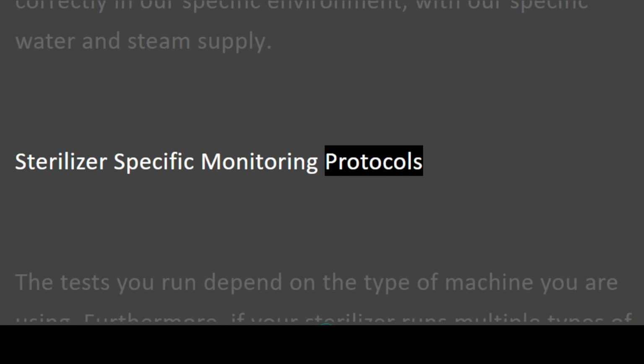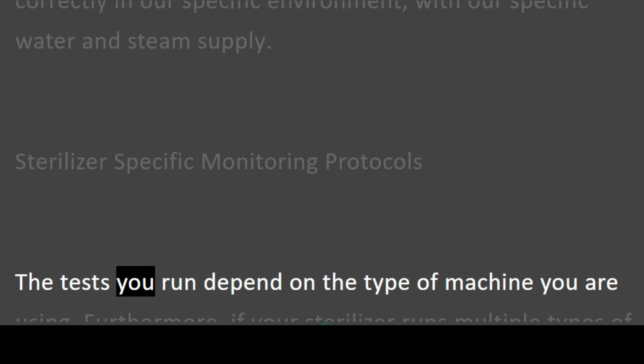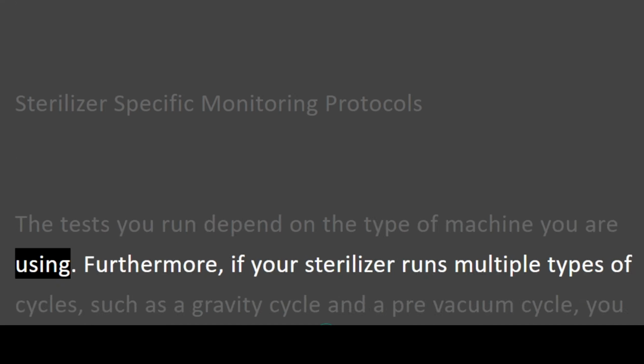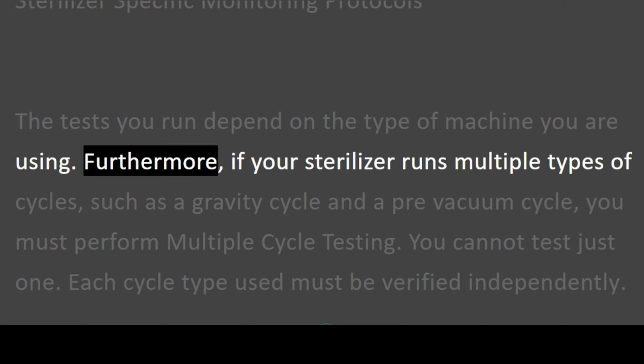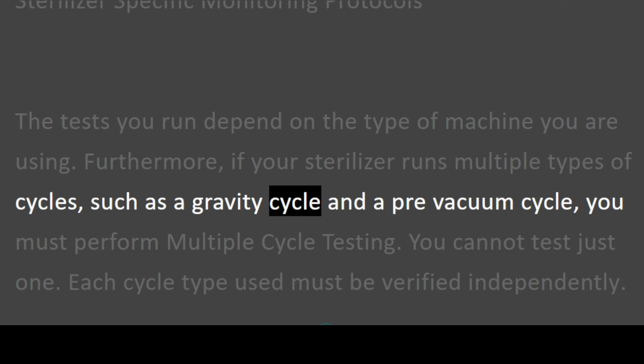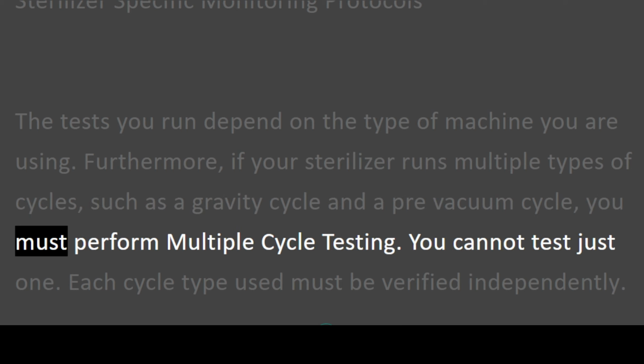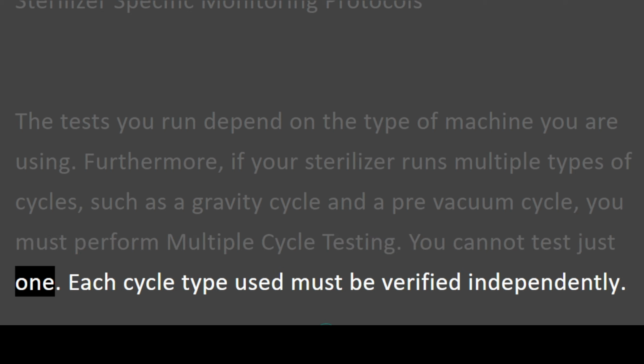Sterilizer-specific monitoring protocols. The tests you run depend on the type of machine you are using. Furthermore, if your sterilizer runs multiple types of cycles, such as a gravity cycle and a pre-vacuum cycle, you must perform multiple cycle testing. You cannot test just one. Each cycle type used must be verified independently.